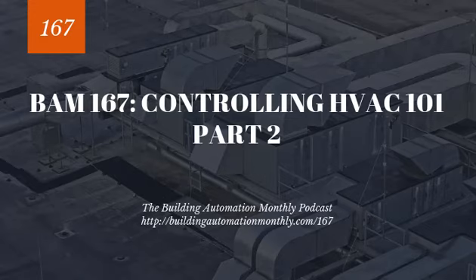So we always have to think that safeties come first. Our pressure sensors, our low temp alarms, our smoke alarms, all of these safeties come first. And these are both going to be hardwired interlocks like we talked about, I think it was episode 164. But these are also going to be software where we look at the conditions of these safeties, what state they are in, and then make a decision. This will become more clear when we talk through some sequences related to our airside systems.